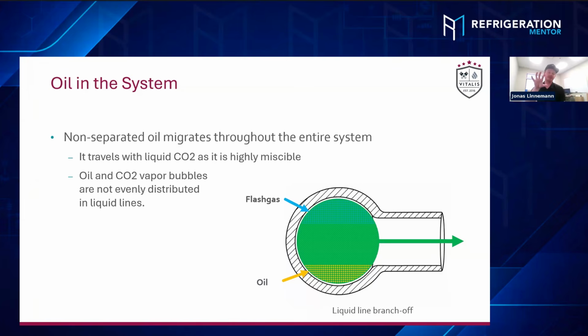Yeah, but the oil effect is not very big. The bigger effect here is definitely the flash gas. The flash gas, yeah. But if you branch it off to the bottom, the first evaporators will just have a little higher amount of oil inside. So the risk of trapping more oil inside the evaporator, losing maybe some efficiency on those evaporators, is a bit higher due to oil, not due to liquid, because the liquid will be very, very pure at these evaporators. But you essentially just increase the amount of flash gas to the very end, and then the last evaporators in line don't get the capacity anymore.